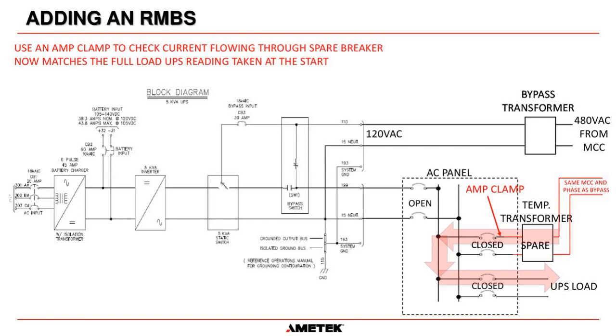Another question: how many AC panels can be connected to the output cable of a UPS? That is completely up to you, and you just have to stay within the rating of the UPS. So if it's in this drawing here, it's a 5 kVA UPS.